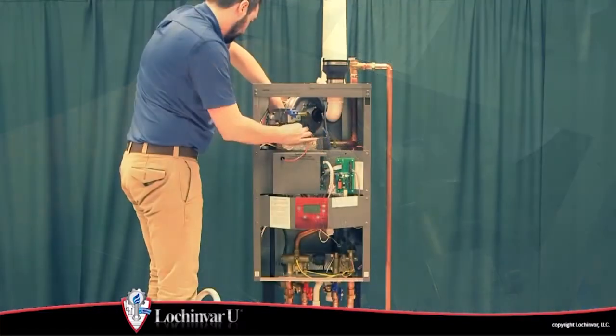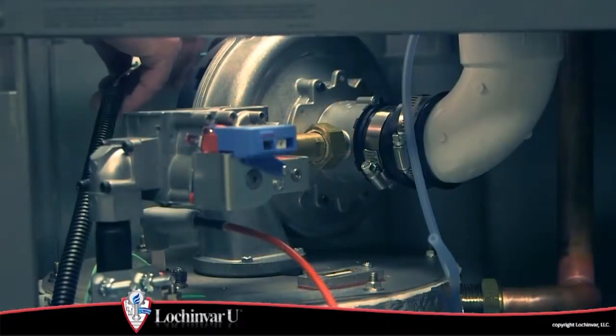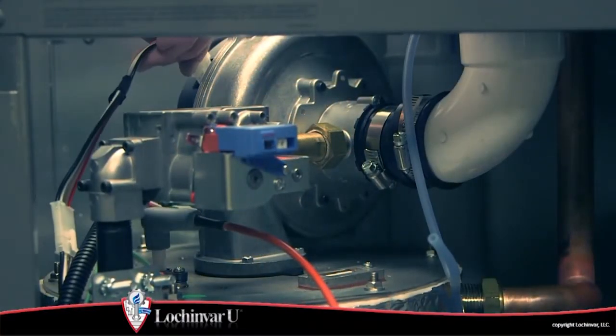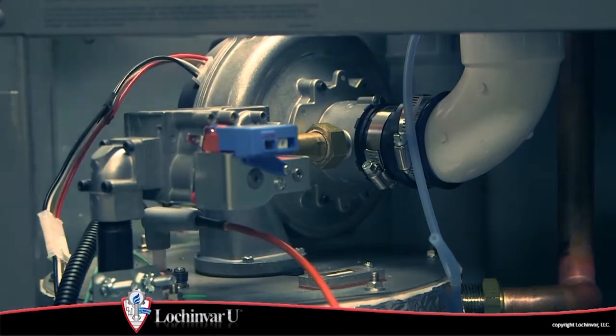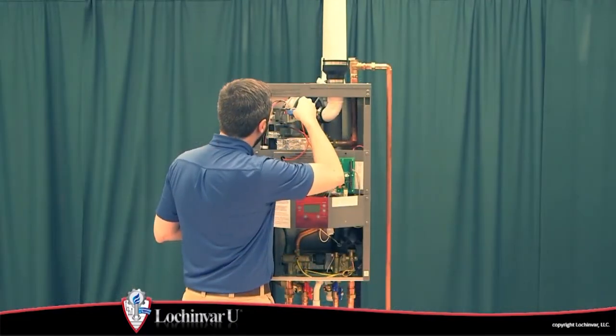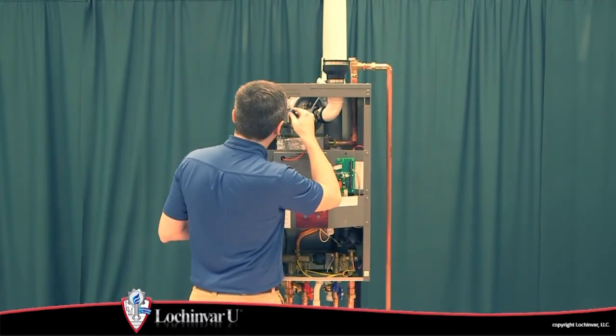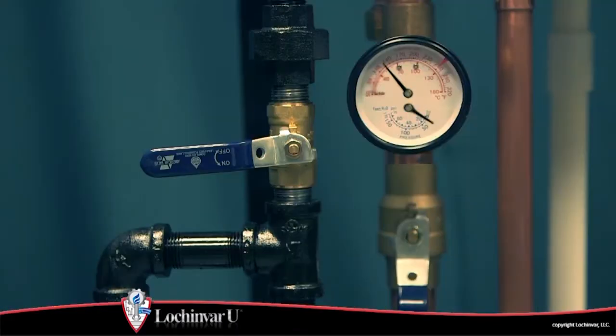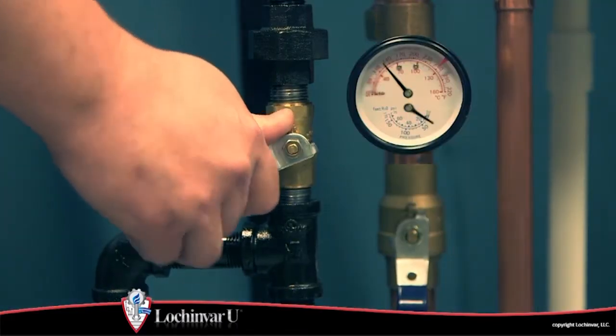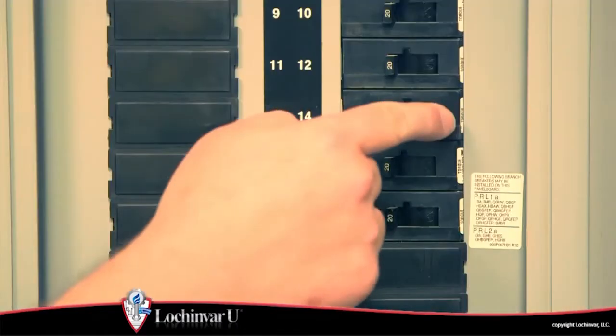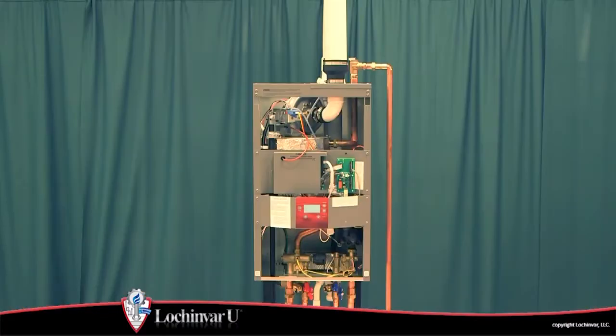Now, reconnect the wiring from the spark igniter and ground terminal, the 2 wiring harness connections on the combustion blower, and the gas valve wiring harness and reference hose to the gas valve. And turn on the main gas supply to the unit at the external main manual gas valve. Now turn on the main power to the unit.